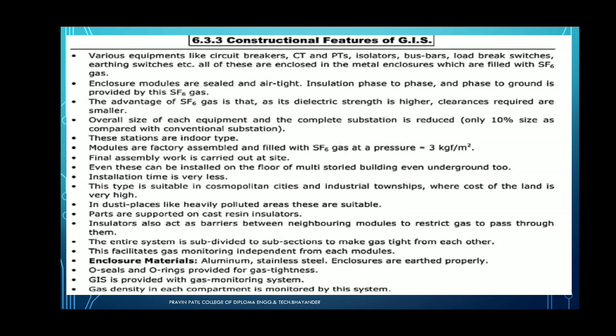This type is suitable for locations such as cosmopolitan cities, industrial townships where the cost of the land is very high. In dusty places like heavily polluted areas, the gas insulated substation is suitable to install. Parts are supported on the cast resin insulator. Insulator also acts as the barrier between the neighboring modules to restrict gas from passing through them. The entire system is subdivided into subsections to make them gas tight from each other. This facilitates gas monitoring independently from each other.